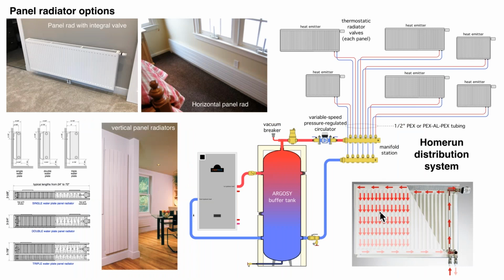Now, panel radiators, one of my favorites. This panel radiator right here is about 2 feet high, 5 feet long. It's being supplied by a geothermal water-to-water heat pump. And it's operating under design load conditions at most 110 degree water. It's got a thermostatic valve up here. This allows each one of these heat emitters, these radiators, to be an independently controlled zone.